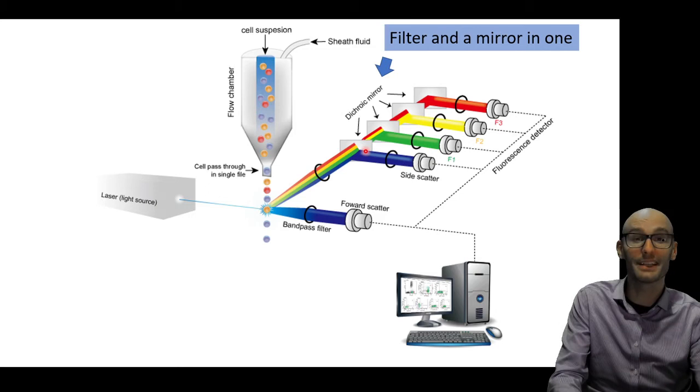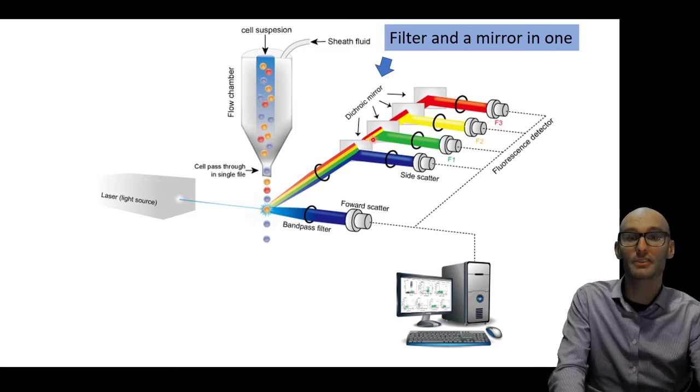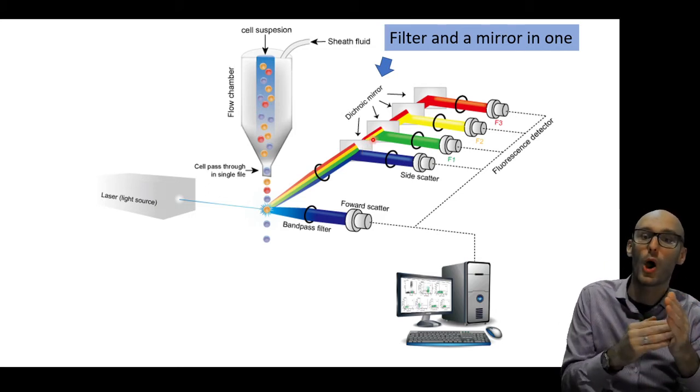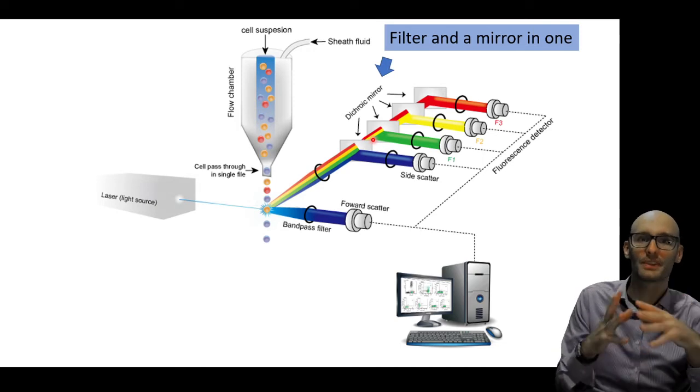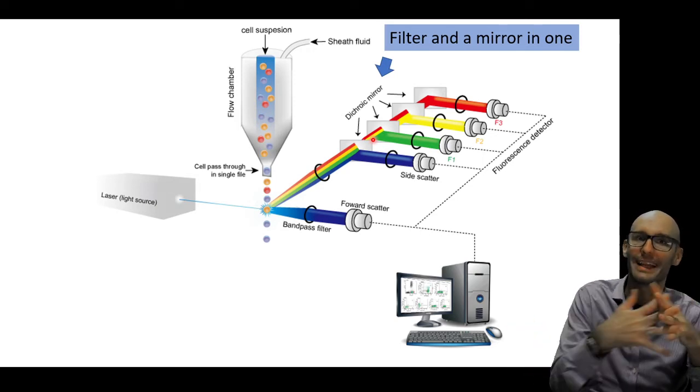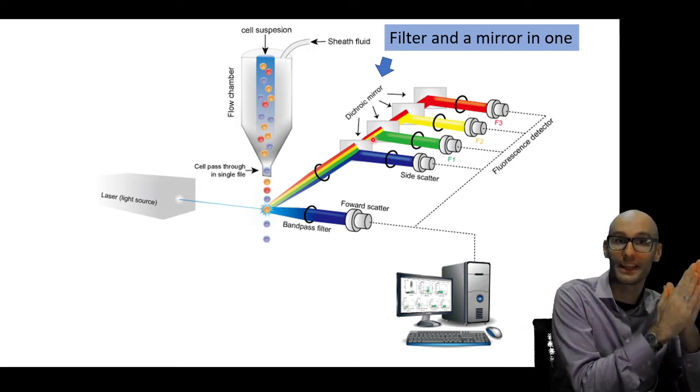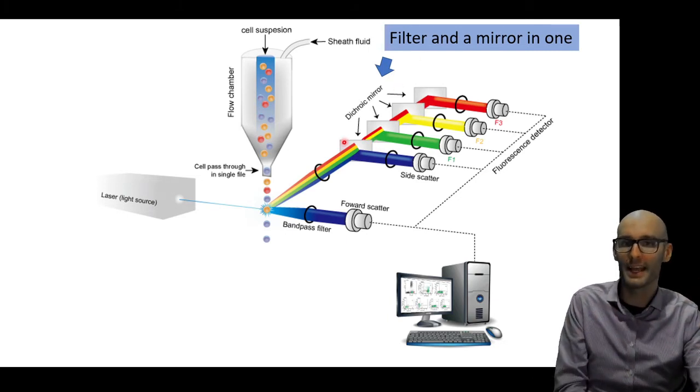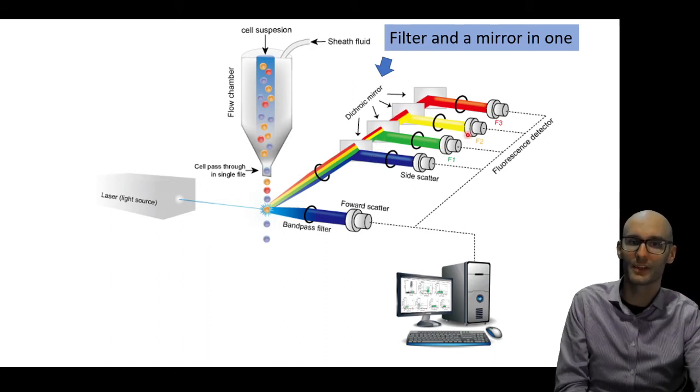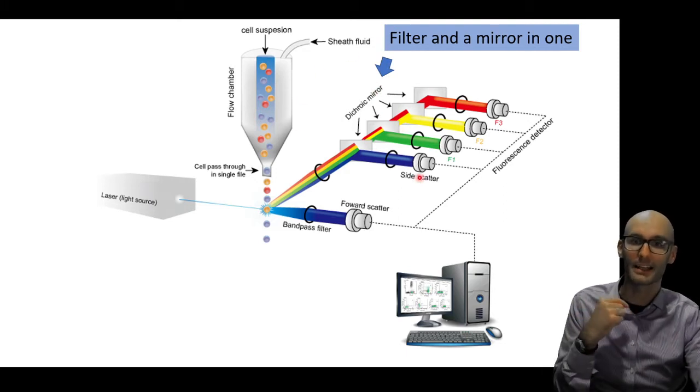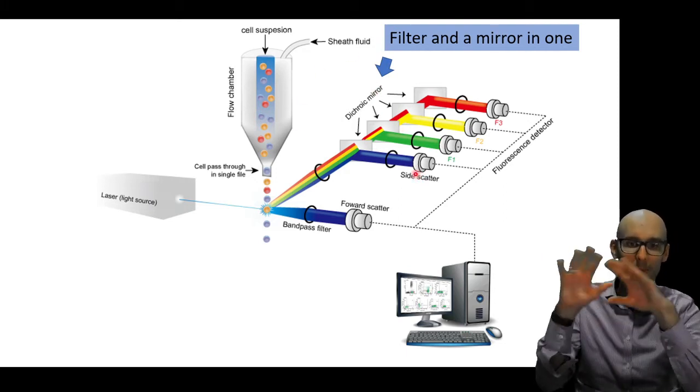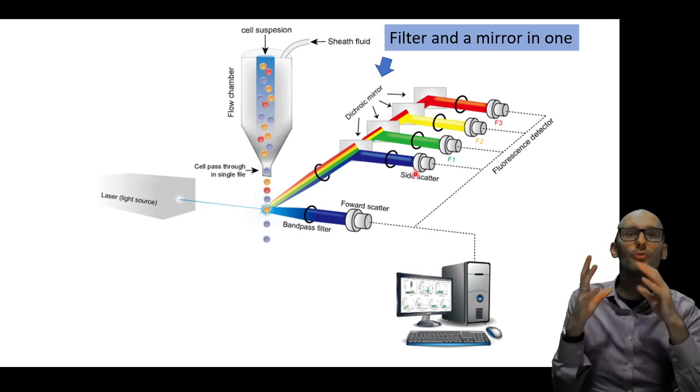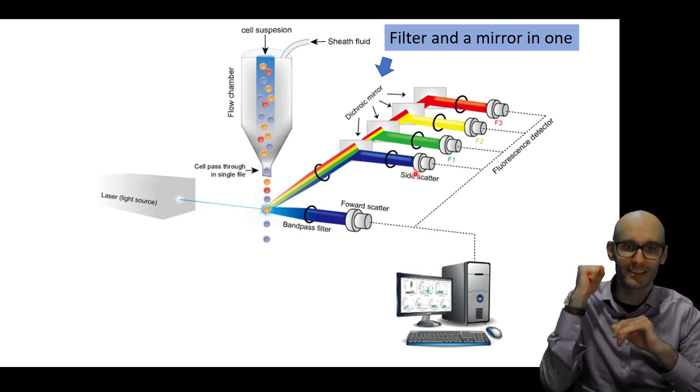Now, in the actual machine, instead of a filter, often there is a mirror, and that mirror will only reflect a specific wavelength of light, and it will let all the other wavelengths go through. So here you can see, it acts kind of like a filter and a mirror all in one. This one only reflects blue light, this one only reflects green light, this one only reflects yellow light, and it's such a clever technique that allows us to look at a number of fluorescent colors all simultaneously on a single cell.